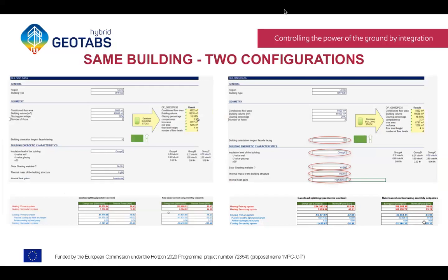You can see at the bottom what this gives in annual estimated consumption based on ideal predictive control, and the resulting monthly set points. For the same building, just by changing those parameters, it can be better or worse, but we see the annual consumption can be increased. At an early stage, you can show your client the effect on annual consumption and peak demands of just changing the insulation, applying solar shading, or changing the thermal mass, even though it's still the same building.